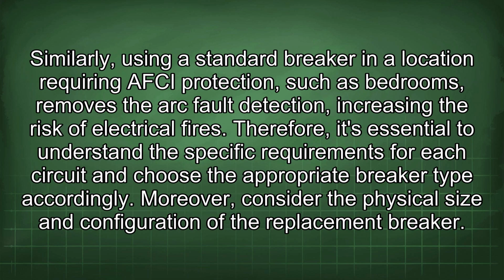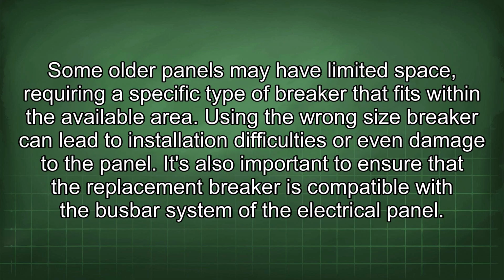Similarly, using a standard breaker in a location requiring AFCI protection, such as bedrooms, removes the arc fault detection, increasing the risk of electrical fires. Therefore, it's essential to understand the specific requirements for each circuit and choose the appropriate breaker type accordingly. Moreover, consider the physical size and configuration of the replacement breaker. Some older panels may have limited space, requiring a specific type of breaker that fits within the available area. Using the wrong size breaker can lead to installation difficulties or even damage to the panel.